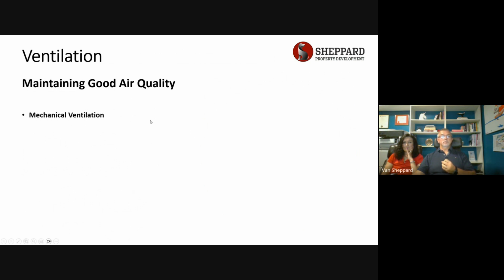So mechanical ventilation is basically having a system in your building specifically designed to exchange fresh air from the outside with stale air from your building. You want that ventilation to be balanced. So we go back to the three images I showed you before for air changing, for convective heat loss, and you had stack effect, which is air going out the top and coming in the bottom, and you had pressure from one side to the other. You don't want to create your own stack or pressure gradient across your walls, so you want your ventilation to be balanced. You want to try to keep the building as close to neutral pressure as you can, because you don't want to encourage leakage other than through your mechanical ventilation system.